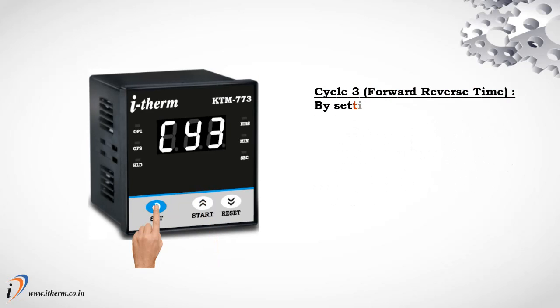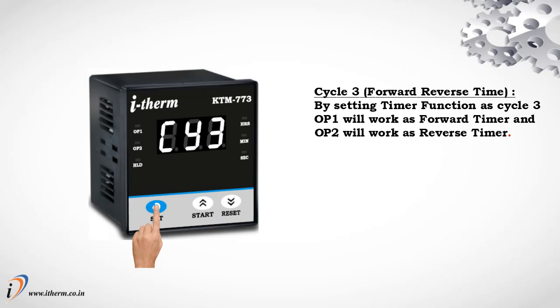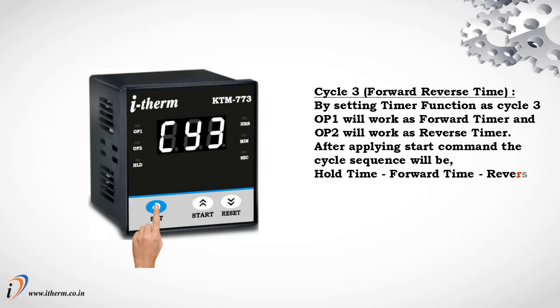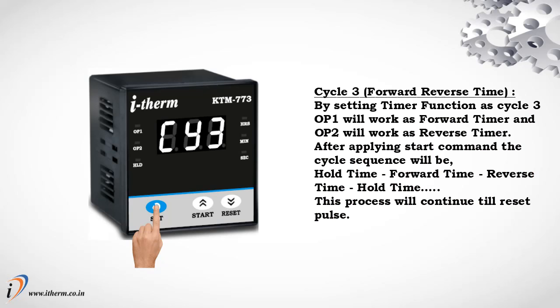Cycle 3, forward reverse time. By setting timer function as cycle 3, output 1 will work as forward timer and output 2 will work as reverse timer. After applying start command, the cycle sequence will be: hold time, forward time, reverse time, hold time. This process will continue till reset pulse.